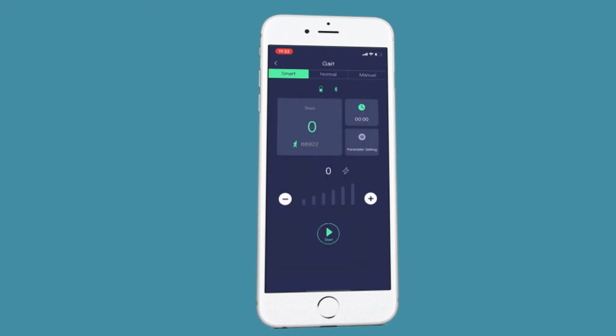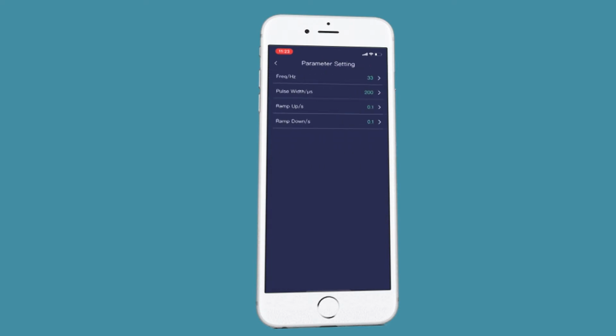All right. Then in manual mode, if you click Start, you'll see a green button, and that is what you will press for stimulation. So first, you increase the intensity to an appropriate motor response, and then every time you press and hold the green button that says press, it will manually stimulate the patient as you're taking them through a treatment. And you press and hold to end that mode. There are your parameter settings. Again, they can quickly be changed.